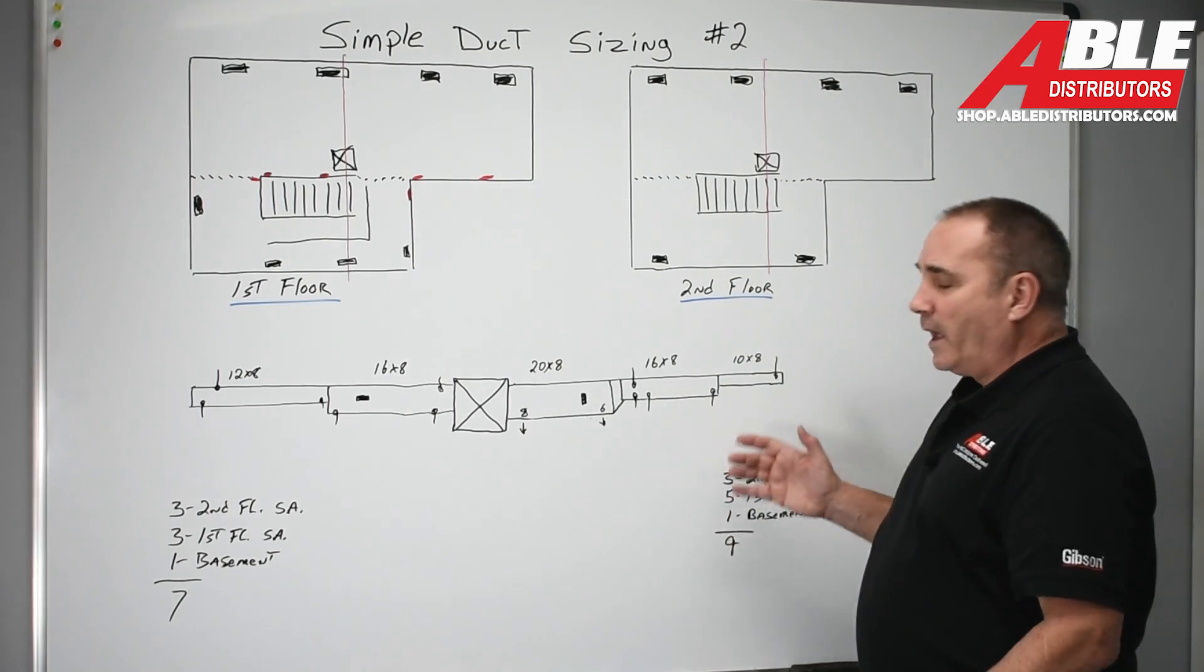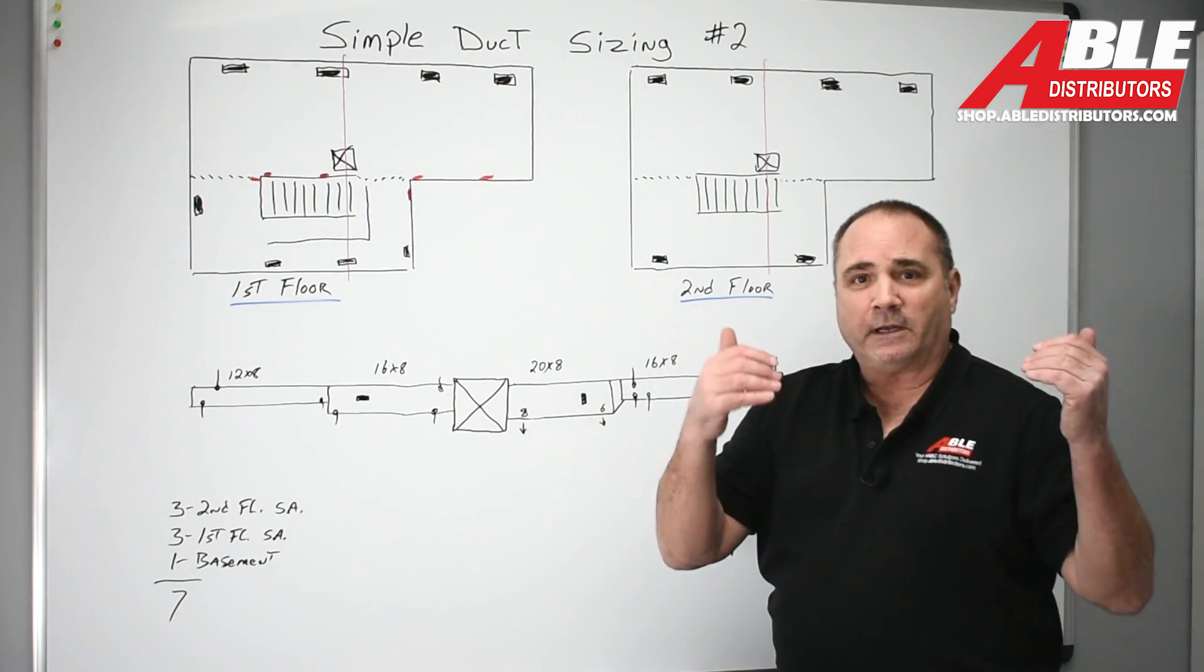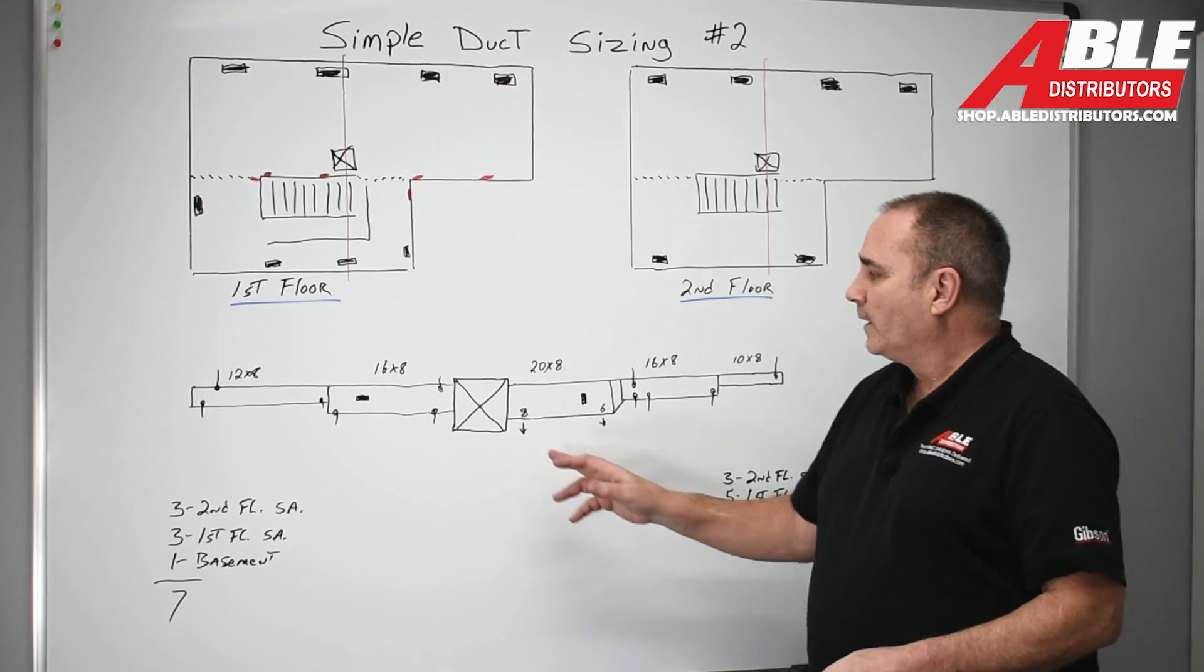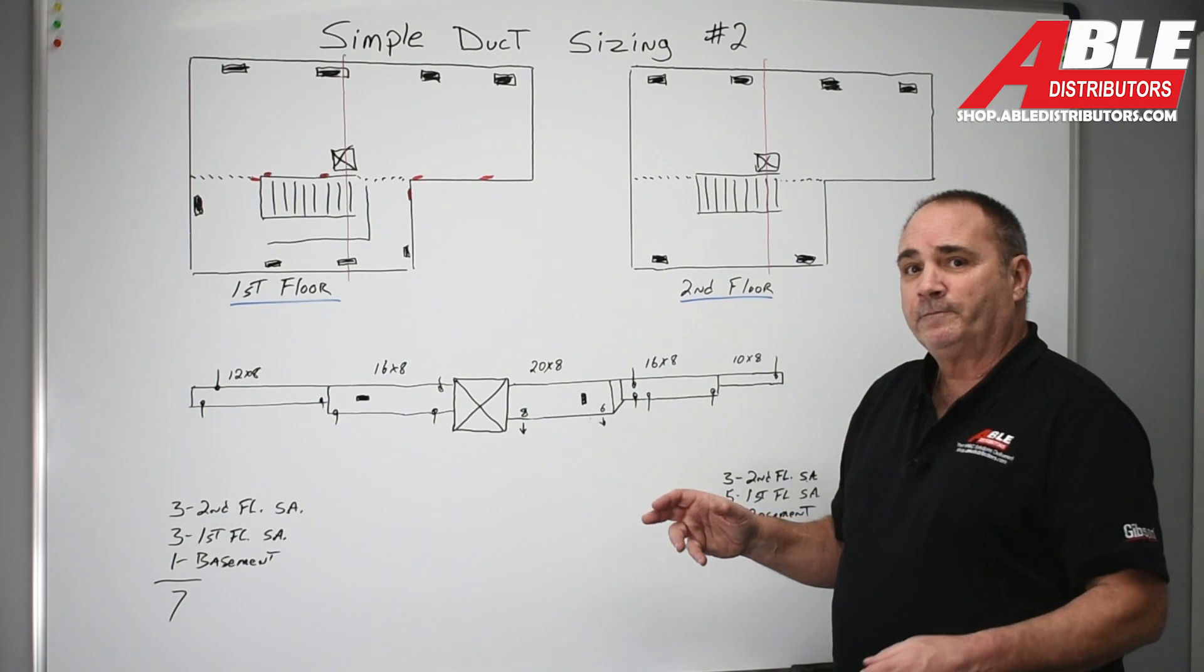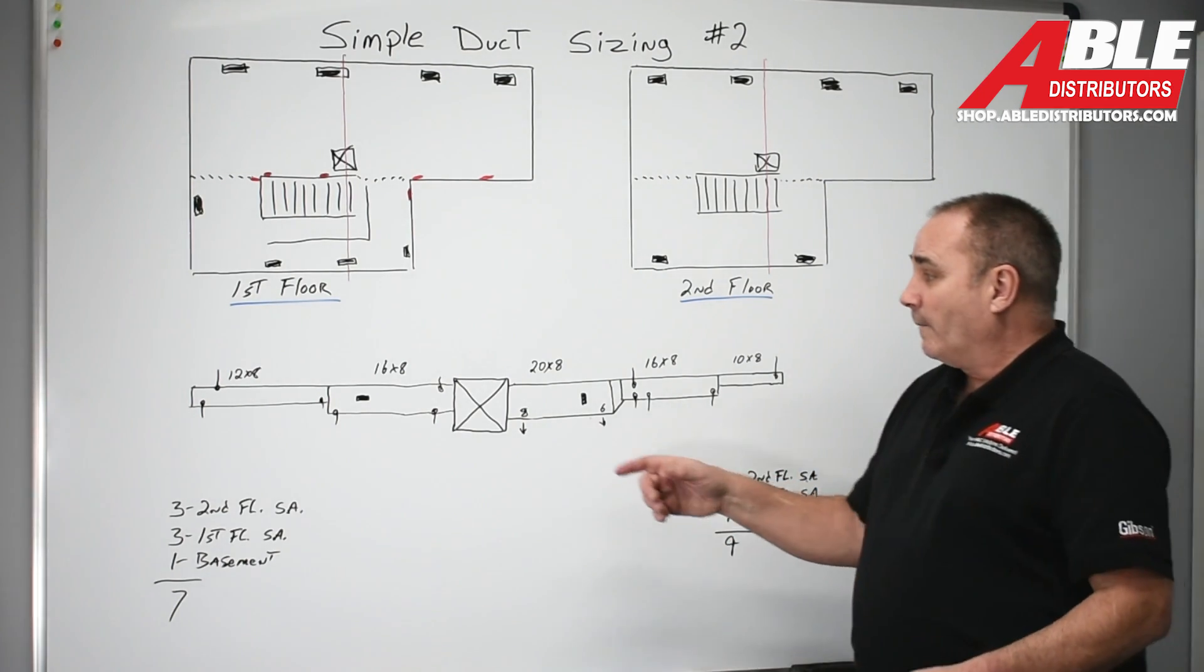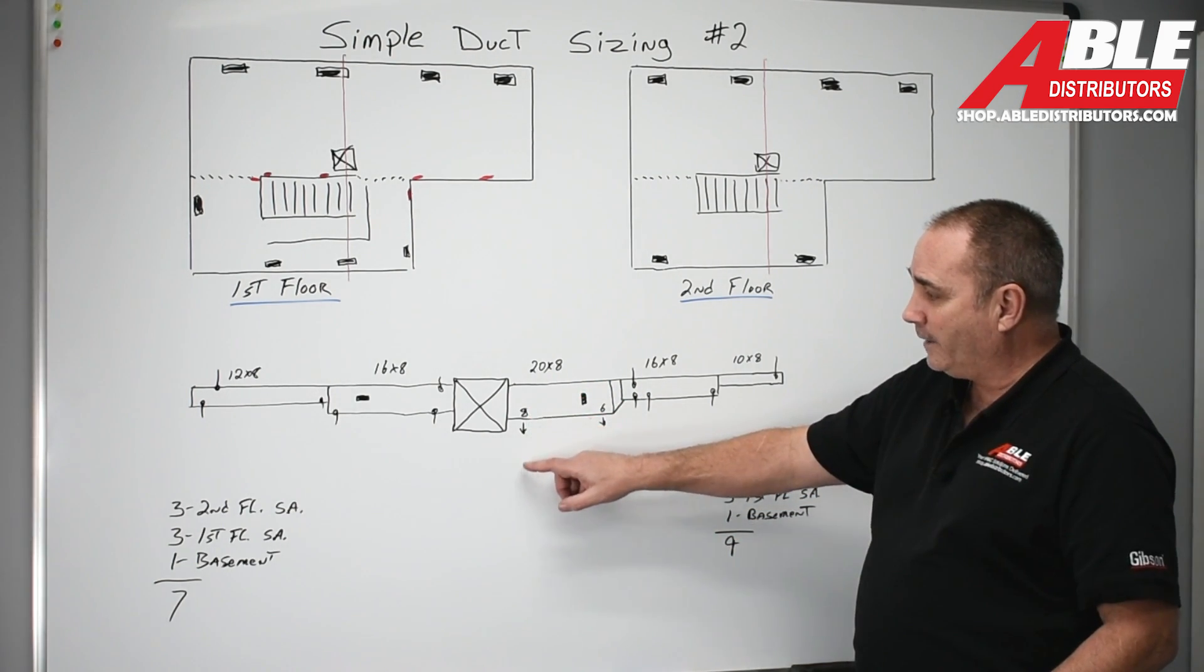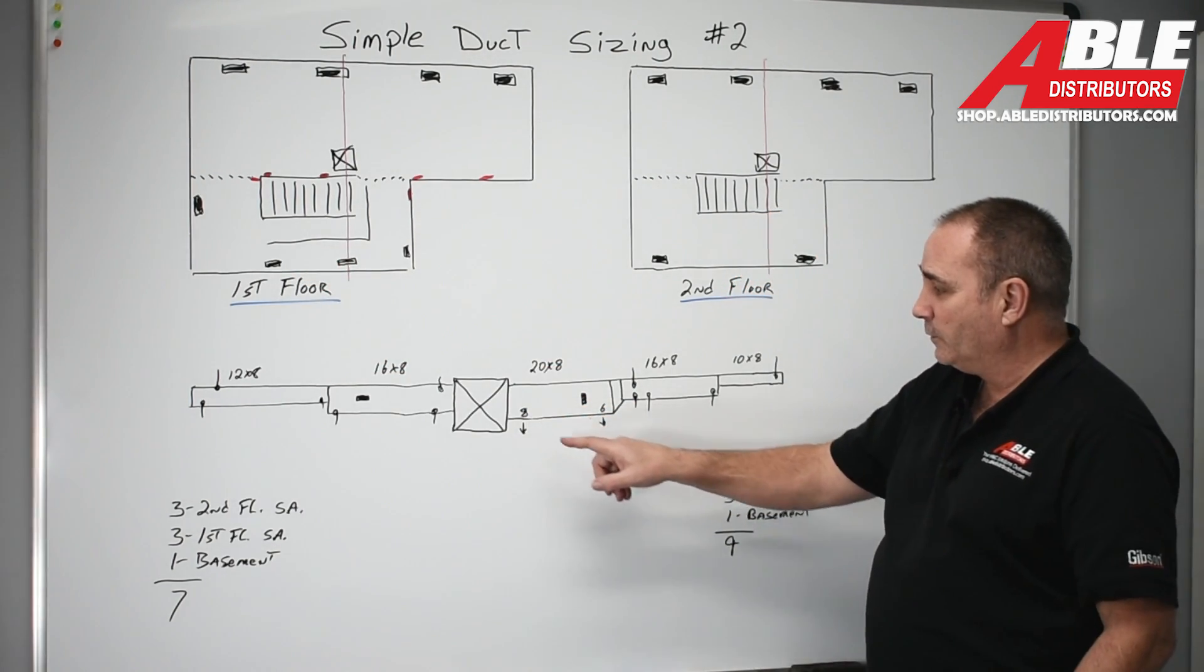Nine supplies - if I use my trusty ductulator it tells me at point one it's about 110 CFM per opening. That's the max they're capable of. So I have to make sure that that first piece of duct is capable of 990 CFM. 20 by 8 is more than capable and off that 20 by 8 I'm going to pull off an 8 with two first floor supplies. So that's one, two.